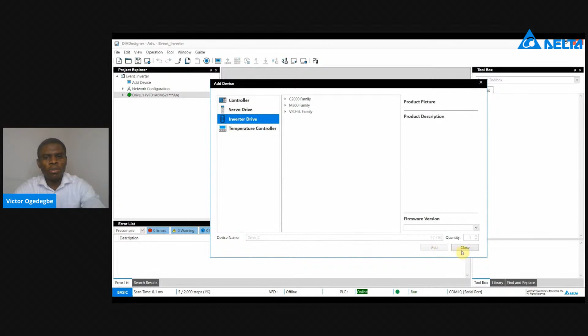One of the features I'd like to share with us that DIADesigner-Ax offers for your inverter is one software for programming both the VFD function, the VFD parameter, as well as the internal PLC of the VFD, of the inverter. So if you expand the VFD function, with this DIADesigner-Ax, it's possible to configure the VFD. If you go to parameter settings, here, you can easily set the parameter of your inverter. You can select single parameter. You can select group parameters. And also, it's possible to edit a single parameter and download a single parameter.